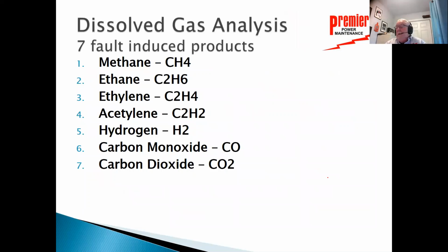Then there is another set of tests that you should also do. It's called dissolved gas analysis. And these are sample tests. There's a test taken out with a syringe on your transformer. And it's not looking at the quality of the oil. It's actually looking at how your transformer has been operated.